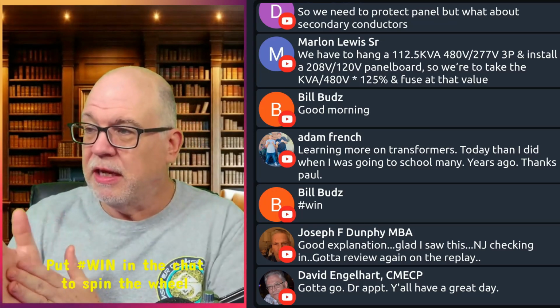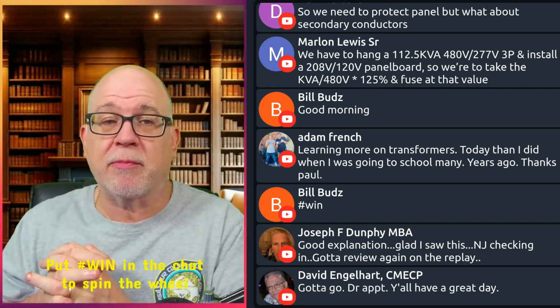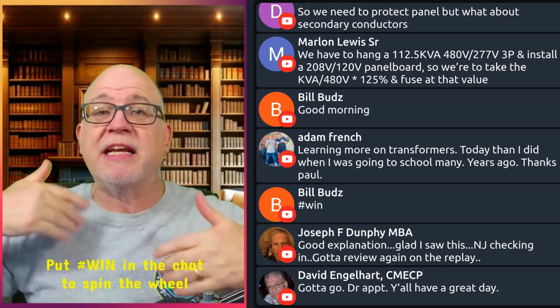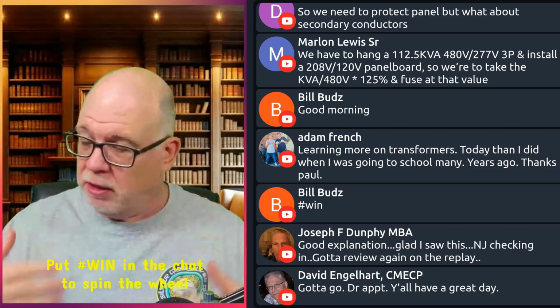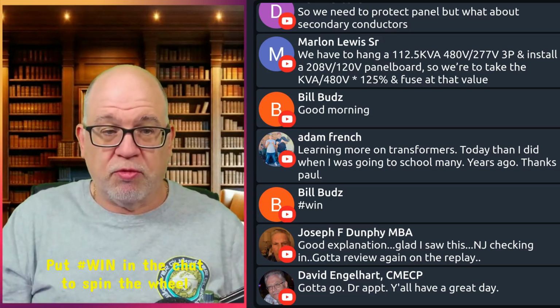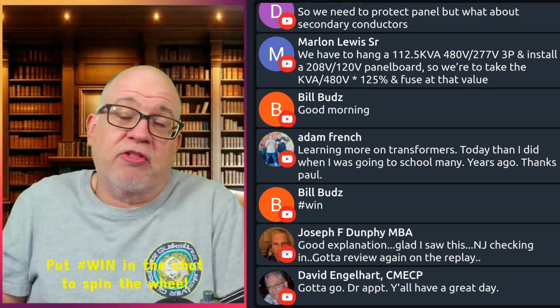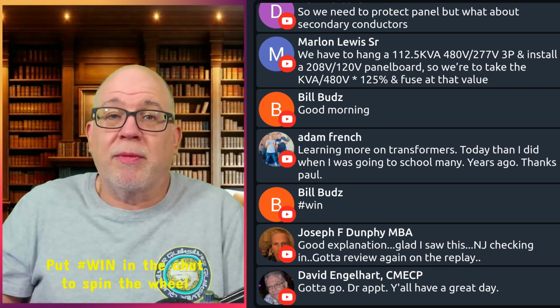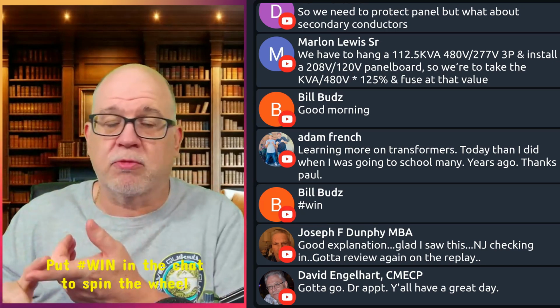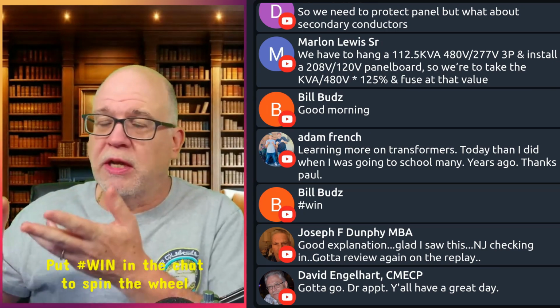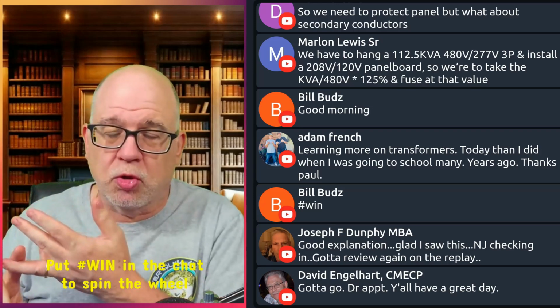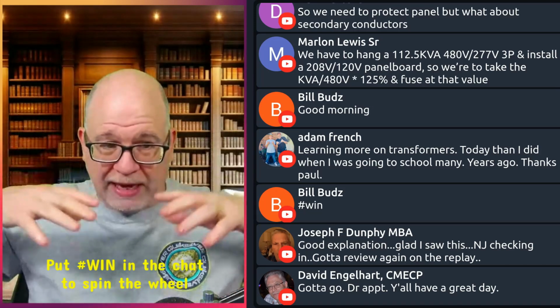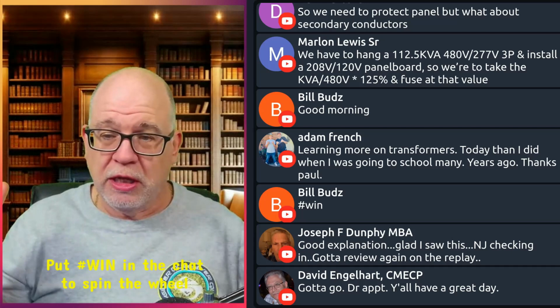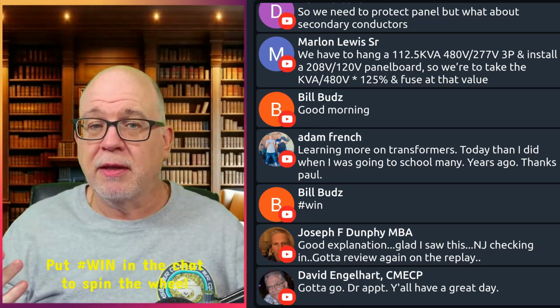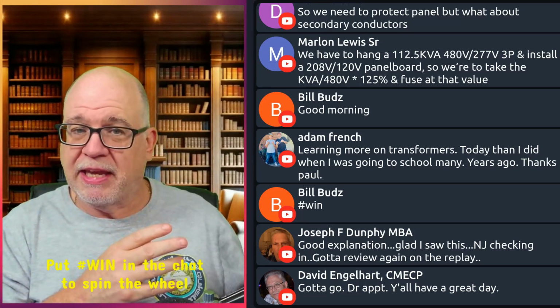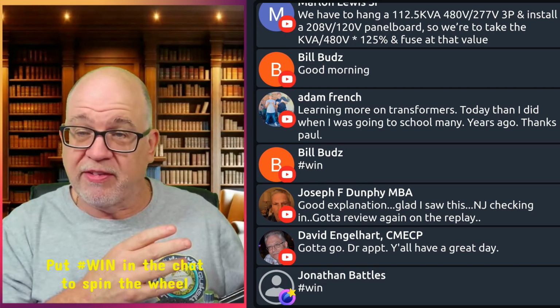That's what we saw when we looked at the code, when a panel board is supplied through a transformer. So then we're dealing with the everyday stuff that you and I do. Primary protection, transformer, panel on the load side or secondary side of the transformer, and we're going to terminate it into a breaker. And we're going to follow the 10-foot rule. We're going to follow the 25-foot rule. If it's outdoors, we're going to follow the unlimited rule, all those type of things, okay? So we're back to where we are, our normal.